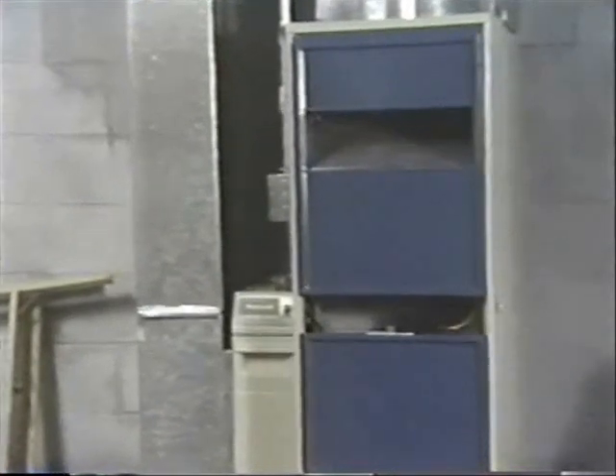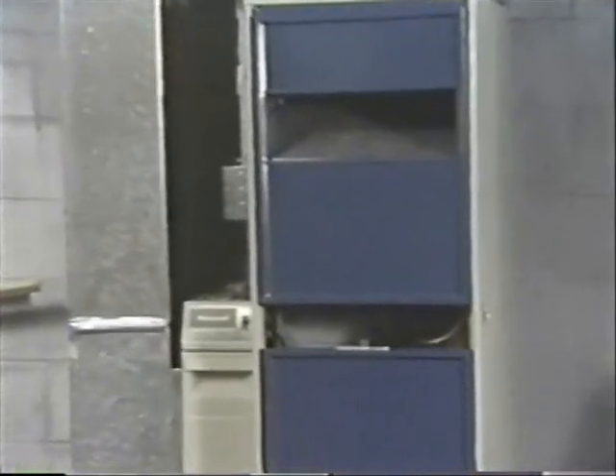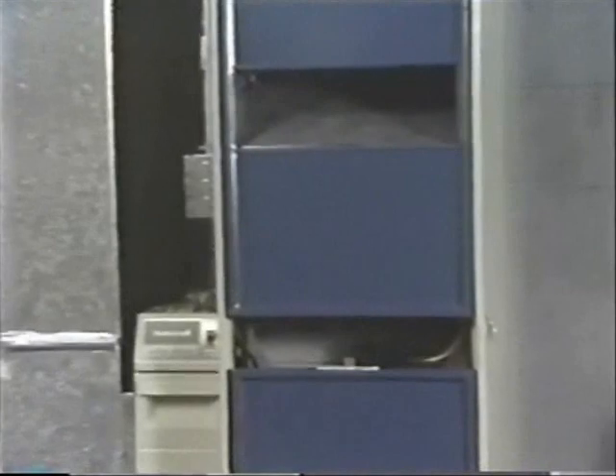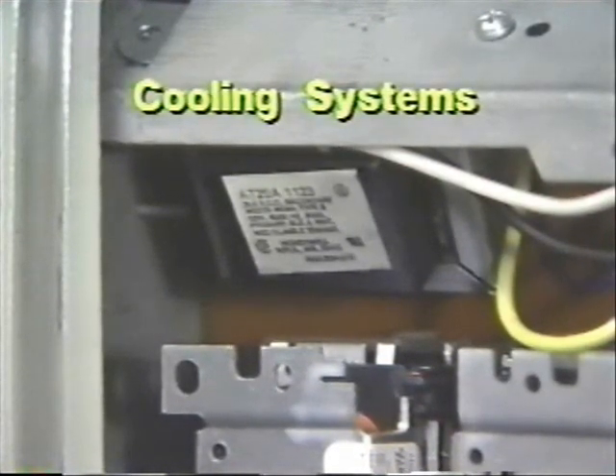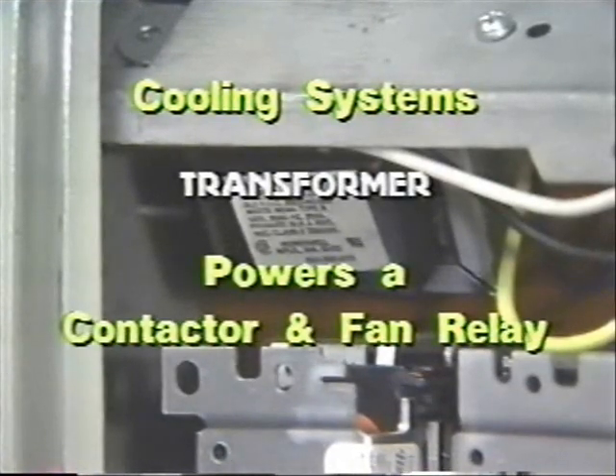Every air conditioning system has two basic elements: the refrigeration equipment itself and the low-voltage circuit which controls that equipment. A transformer serves as the power supply for the control circuit by stepping down the line voltage. Even in simple cooling systems, control circuits pull a heavy load. At minimum, the transformer has to power a contactor and a fan relay. The contactor takes the most power. It's a heavy-duty switch that turns on the compressor motor and often the condenser fan too.